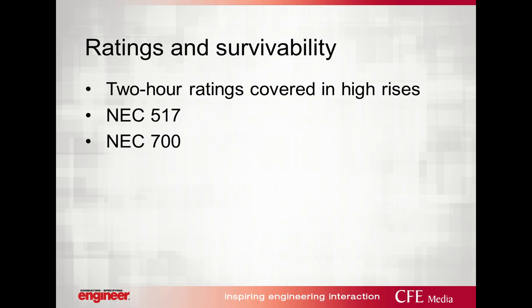Ratings and survivability. I'm going to pass this over to Rich for a few minutes. Yep, so we discussed 2-hour rated cable assemblies in a high-rise application, and they're going to apply here as well. We want to note that NEC 517.31 requires that life safety and critical branch wiring be kept separate from other branches, just as Rick had previously mentioned.